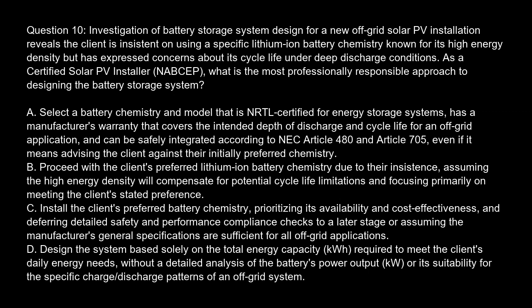Option A. Select a battery chemistry and model that is NRTL certified for energy storage systems, has a manufacturer's warranty that covers the intended depth of discharge and cycle life for an off-grid application, and can be safely integrated according to NEC Article 480 and Article 705, even if it means advising the client against their initially preferred chemistry.